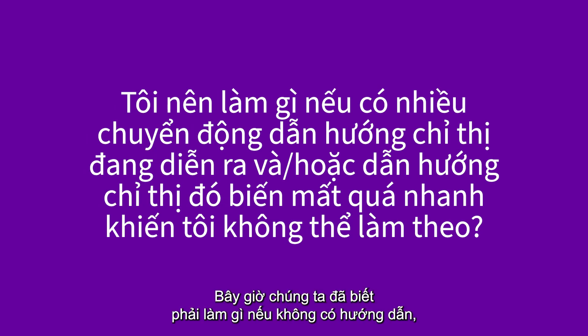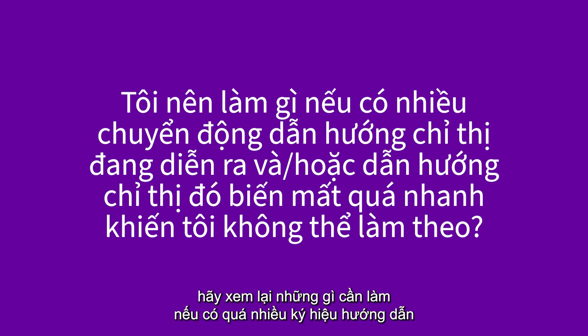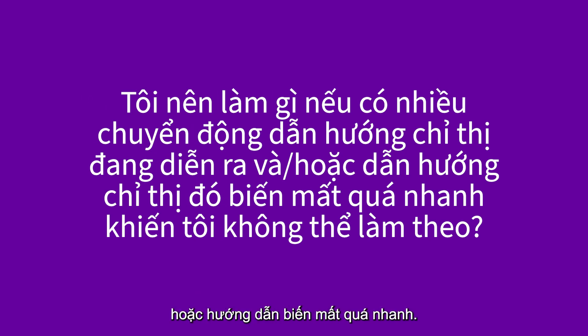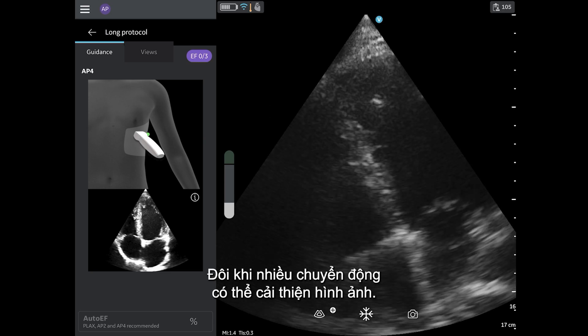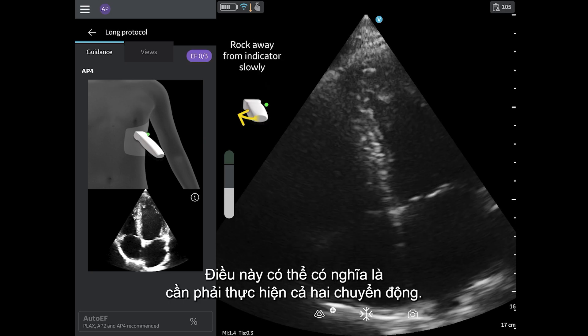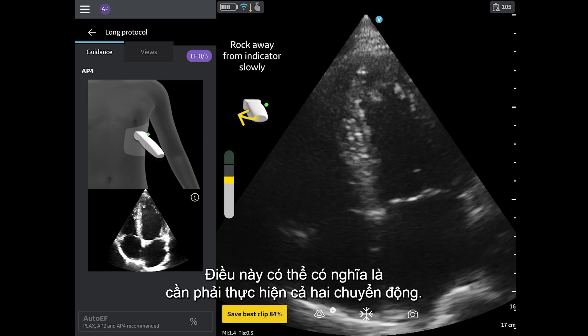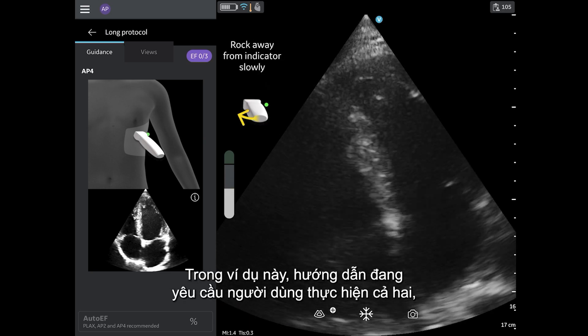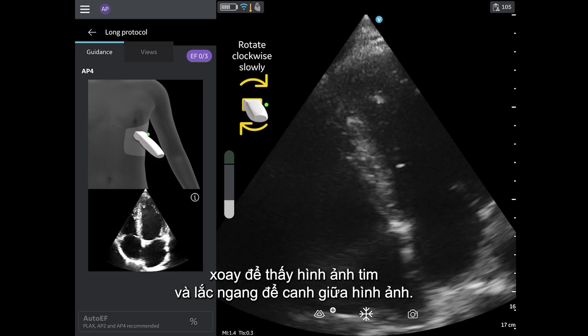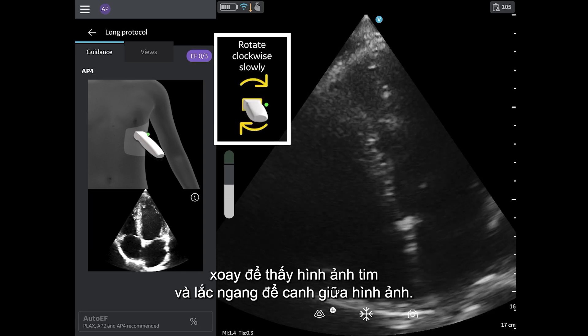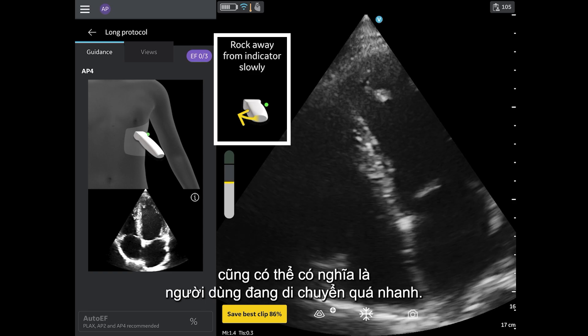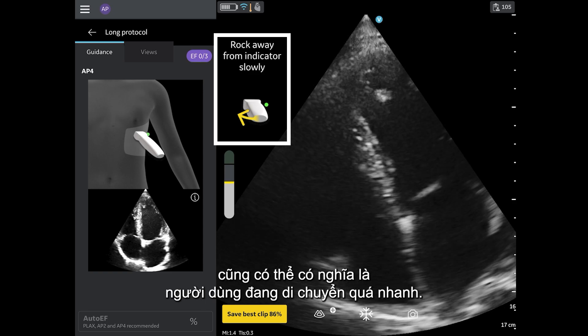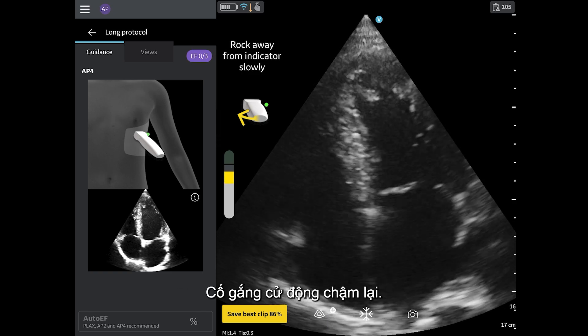Now that we know what to do if there is no guidance, let's review what to do if there is too much guidance, or it disappears too quickly. Sometimes, more than one movement can improve the image, which may mean that both movements need to occur. In this example, the guidance is directing the user to both rotate to see the heart, and rock to center the image. Having multiple movements appear may also mean the user is moving too quickly — try to slow down your movements.